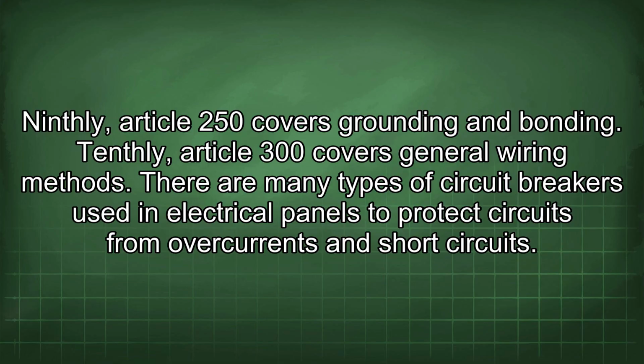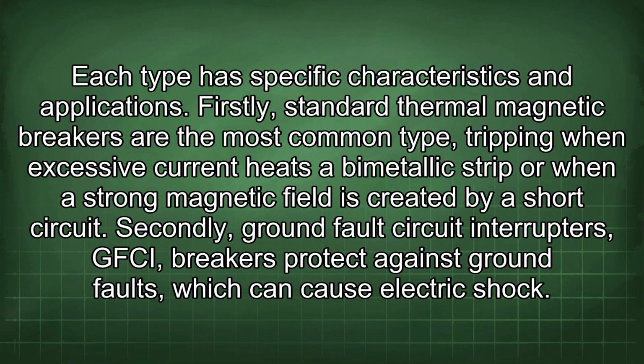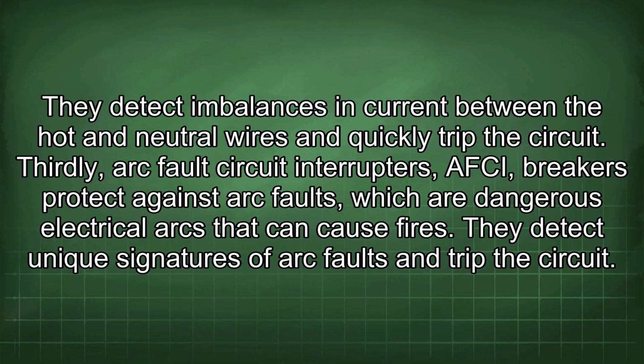There are many types of circuit breakers used in electrical panels to protect circuits from overcurrents and short circuits. Each type has specific characteristics and applications. Firstly, standard thermal magnetic breakers are the most common type, tripping when excessive current heats a bimetallic strip or when a strong magnetic field is created by a short circuit. Secondly, ground fault circuit interrupters (GFCI) breakers protect against ground faults, which can cause electric shock. They detect imbalances in current between the hot and neutral wires and quickly trip the circuit.